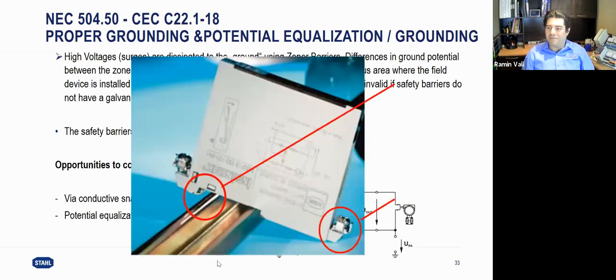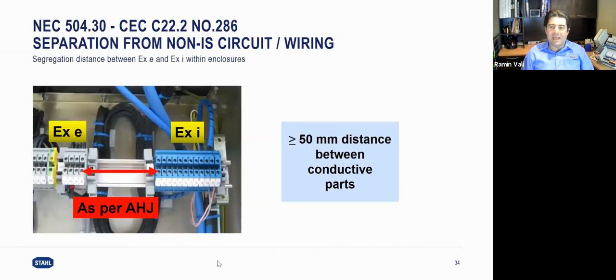And that's why a lot of manufacturers use a stud bar or some sort of mechanical connection to the ground, to make sure they guarantee the connection is properly connected to the ground with a very low resistance situation.